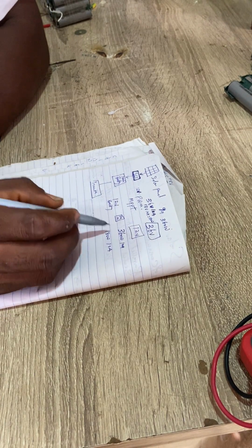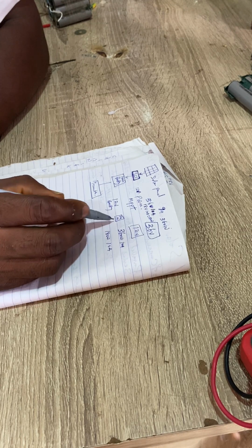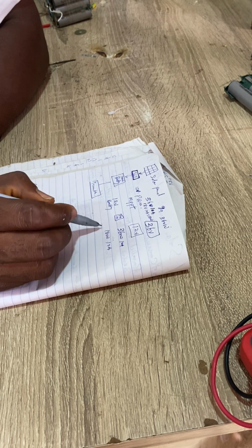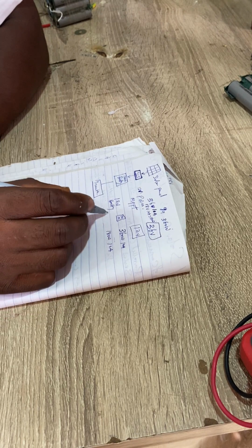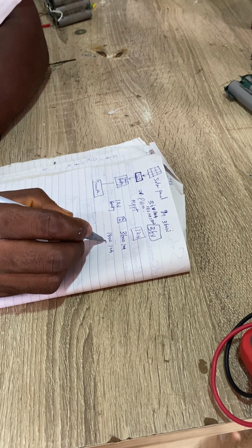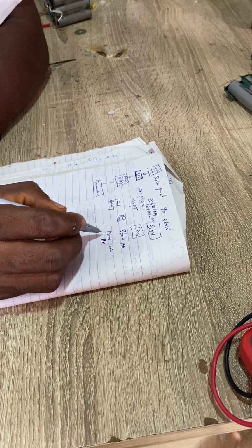Now you would agree with me that if I connect this 180 watt panel to this PWM charge controller that cannot reduce voltage, this battery will charge fine. Let's assume the PWM gives us 8 amps out of these 10 amps. We are still okay.